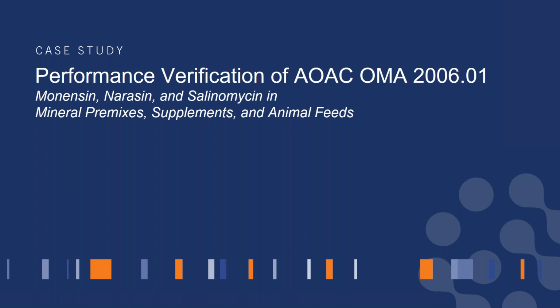Just wanted to give you an example here too. So we have a case study to present for you where there was a request for use of a standard method. When you have a request for a certain type of testing, you should take a look at checking the references, review the original validation compliance with ICH-Q2. Perform a gap analysis and perform missing validation steps prior to the transfer method performance verification process.